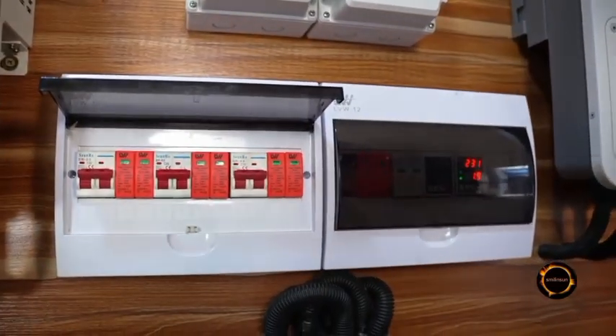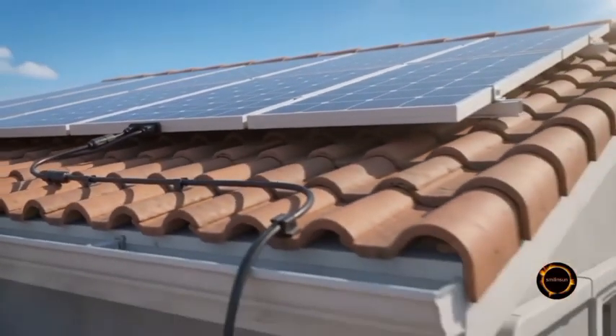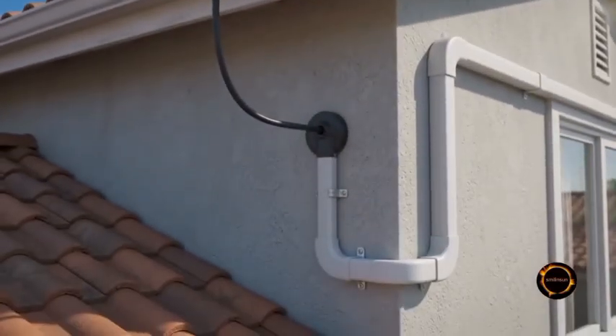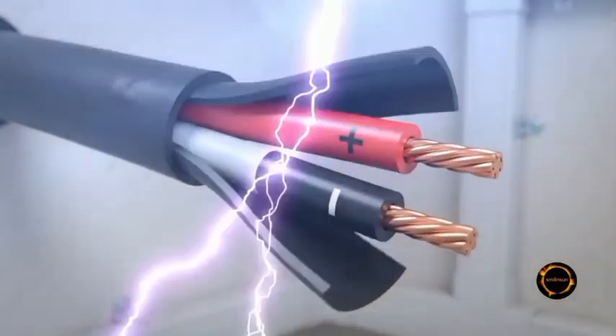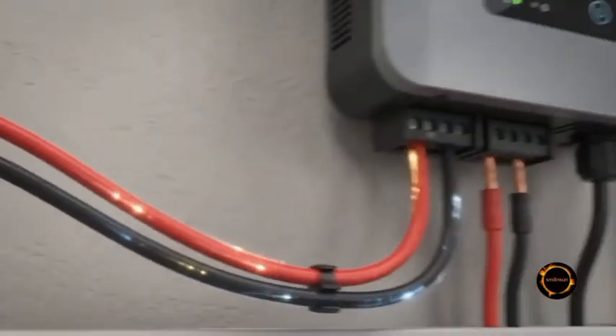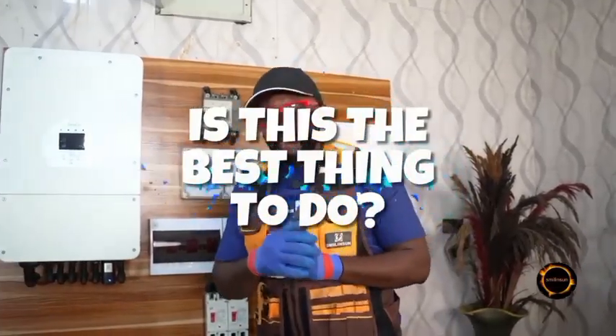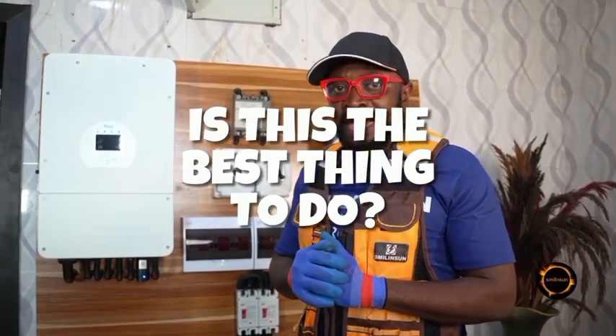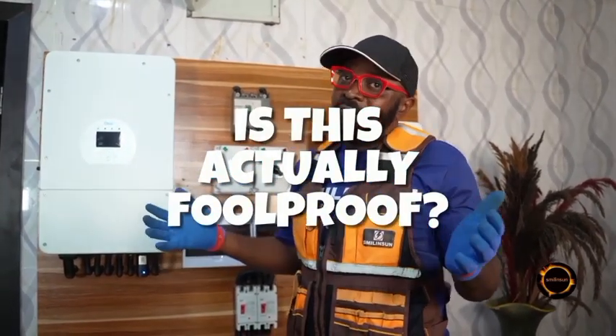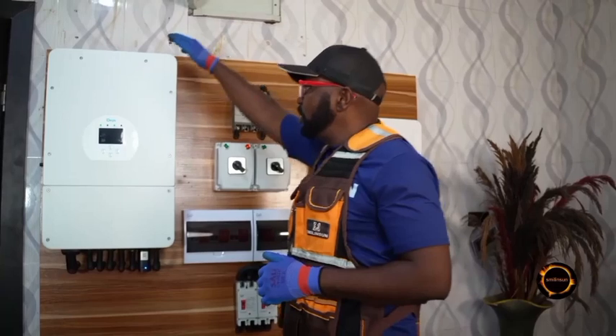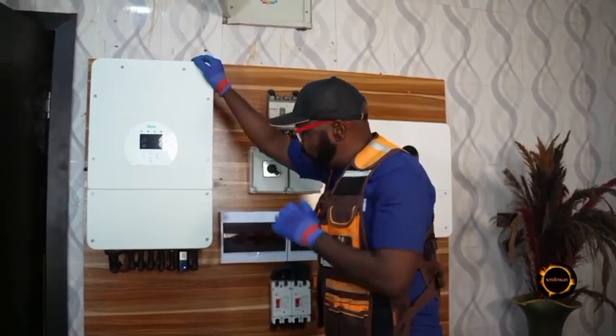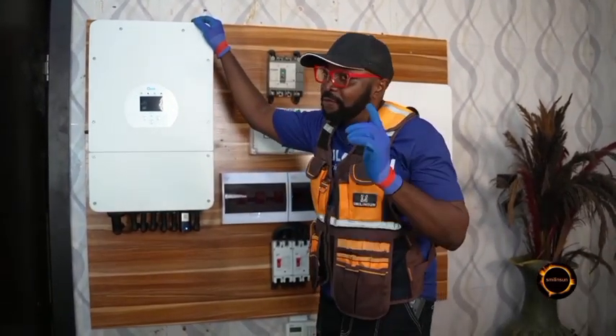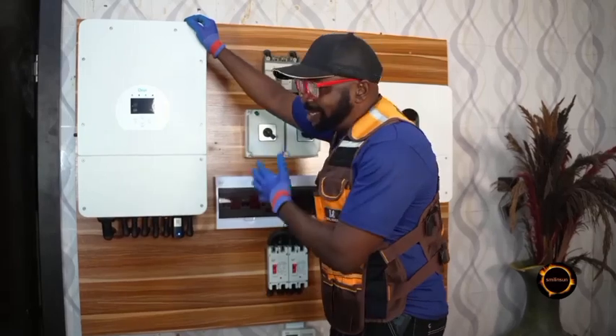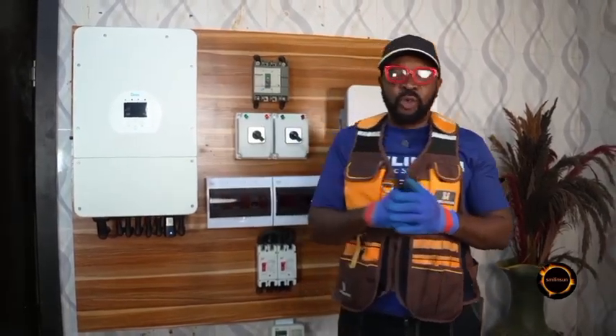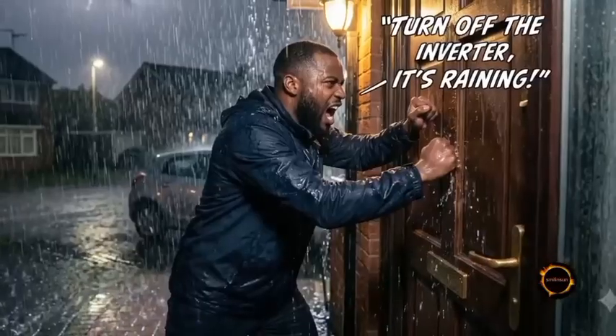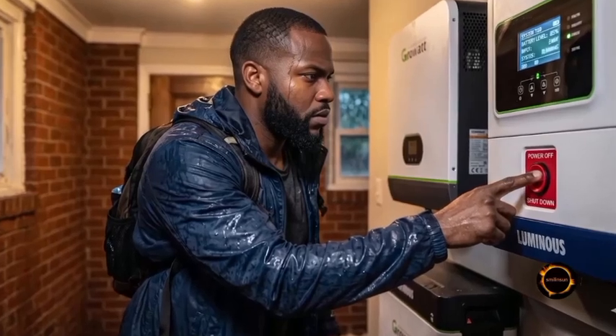This essentially is supposed to disengage the PVs, the solar panels that are connected, because that's an access point where lightning can penetrate your system. But the question is, is this the best thing you should do when it's raining? Is this actually foolproof, that whenever it's raining you run down, switch off your inverter, and then begin to turn off all the breakers? That's very incorrect, because this system is designed to run even when it's raining, since it's practically impossible for you to be at home at all times when it's raining.